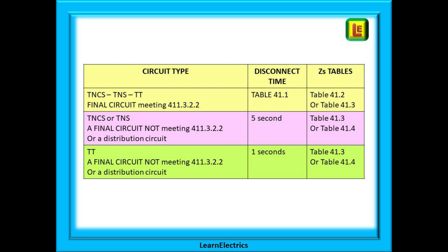We can summarize this in a little table. For any final circuit that meets regulation 411.3.2.2 on page 58, use table 41.1 to find the disconnection time and the two ZS tables shown. For any TN circuit that does not meet regulation 411.3.2.2 — say it's an 80 amp circuit — we apply five seconds as a disconnection time and use the ZS tables shown in the middle row. For a TT circuit not meeting regulation 411.3.2.2, we apply a one second disconnection time and use the ZS tables indicated in the bottom row.